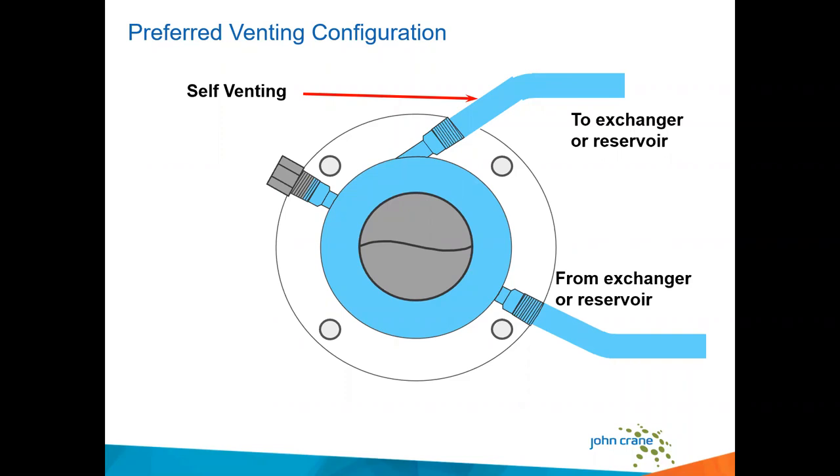This is a different orientation where you're actually promoting self-venting of that cavity at startup. This is part of the mental checklist to go down and look at the orientation of the piping. Is this piping conducive to self-venting? If it's not, do we have mechanisms to manually vent it?